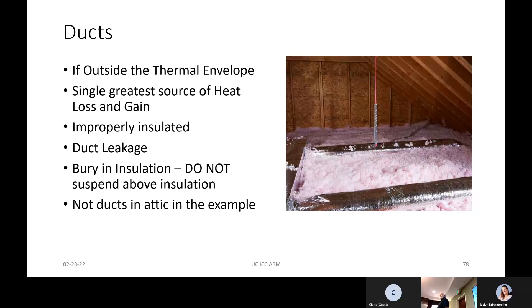When people ask if they have to insulate underground duct, I say you guys make the decision — I don't think you have to. You can bury it in gravel with air spaces in the gravel, maybe heat the gravel a little — make the basement a little more comfortable. Heat doesn't really drain down, it tends to stay at the top. But if you have insulation under a slab, you need to account for it in your load calculation. Under a heated slab I understand the need — we have a greater temperature difference, sometimes heating slabs to 100 degrees.